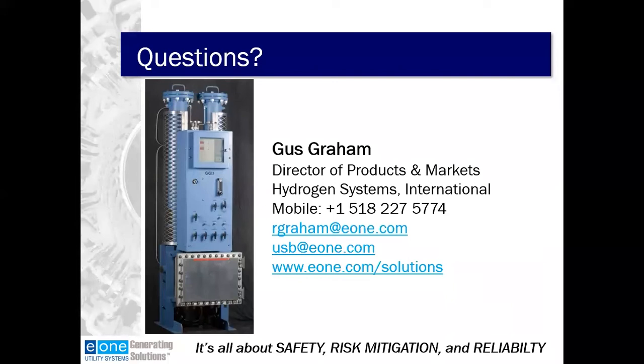N2 can be used, and nitrogen is used more and more in plants in Europe, it seems. One of the considerations for using nitrogen gas is the hydrogen purity monitoring system that you have in place. Certain purity monitoring systems cannot differentiate between nitrogen gas and pure air because of the very close densities and very close properties between oxygen and nitrogen.